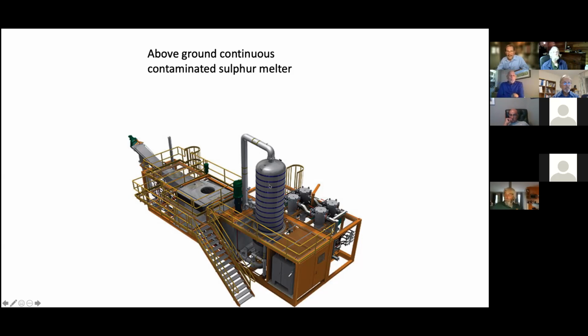And we soak the steam to like 10 bar steam. Typically you melt at about 6 to 8 bar. We put 10 bar steam, and a very high flow rate gave us tremendous agitation, gave us all the melting we needed, and it worked quite well.